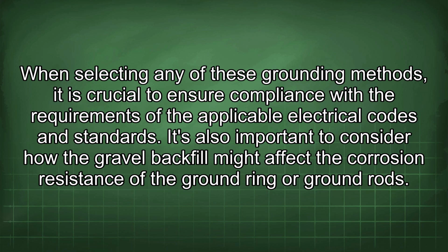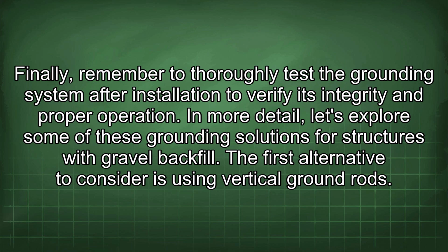When selecting any of these grounding methods, it is crucial to ensure compliance with the requirements of the applicable electrical codes and standards. It's also important to consider how the gravel backfill might affect the corrosion resistance of the ground ring or ground rods. Finally, remember to thoroughly test the grounding system after installation to verify its integrity and proper operation. In more detail, let's explore some of these grounding solutions for structures with gravel backfill.